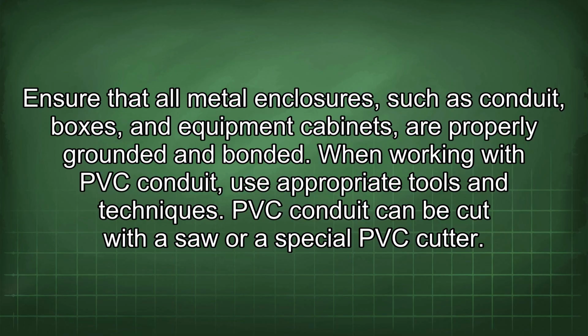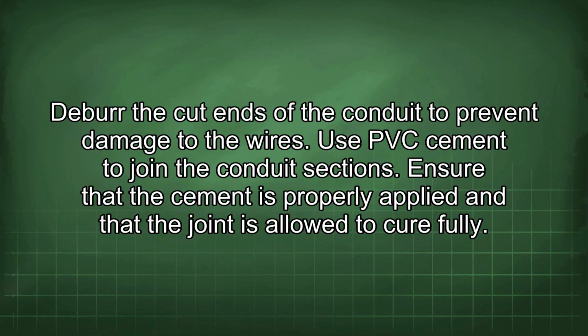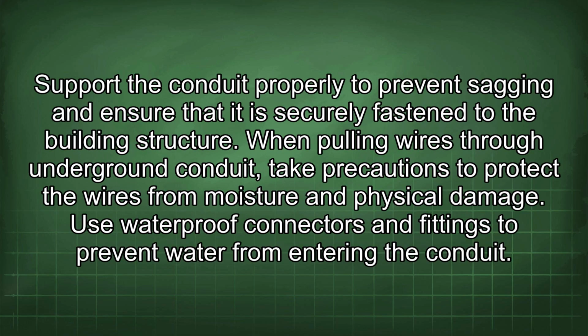When working with PVC conduit, use appropriate tools and techniques. PVC conduit can be cut with a saw or a special PVC cutter. Deburr the cut ends of the conduit to prevent damage to the wires. Use PVC cement to join the conduit sections. Ensure that the cement is properly applied and that the joint is allowed to cure fully. Support the conduit properly to prevent sagging and ensure that it is securely fastened to the building structure.